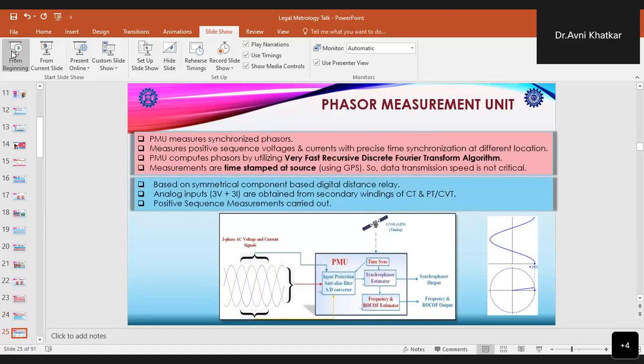So now, what is this PMU? PMU is actually a device, or it can also be a function in a multifunction device, which can produce synchronized phasors, frequency, and rate of change of frequency, that is ROCOF estimates, for the voltage or current signals and a time synchronization signal. These phasor measurement systems trace their origin to the development of SCDRs, that is symmetrical component distance relays, of the early 1970s. And in the early 1980s, measurement systems started using the GPS to synchronize the sampling clocks, which offers a common time reference. And the first experimental PMU was developed at Virginia Tech University in 1988, and Macrodyne was the first company to build the first PMU in 1992.